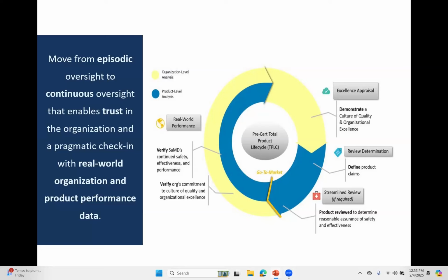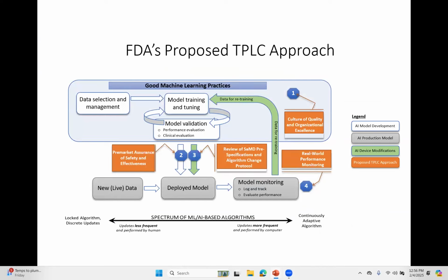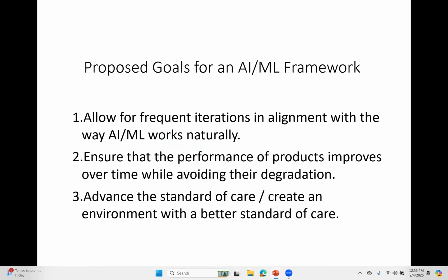So the ability to take a life cycle approach and manage everything up front and throughout and continuously really allows for max value, max compliance, least burdensome approach, because by default, you're ideally going to be setting up your system to track everything and generate the minimal amount of information that you need, but still important. And you can see, going back to the spectrum, you have more frequent updates, less frequent updates. How much monitoring are you going to have to be doing? How much training do you need to implement? This really speaks to how ultimately you're going to be able to prove, if you do make changes, the performance only improves, will only be enhanced.